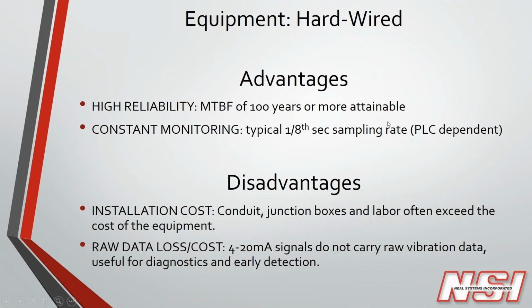So advantages of hardwired solutions, typically you're going to see an MTBF of 100 years or more can be attainable. What that means is you're not getting 100 years out of a sensor, but if you have 100 sensors in your facility and one failed per year, you'd be in line with a 100-year MTBF. And then for these hardwired solutions, you've got constant monitoring available. So your sample time depends on your PLC, but you have constant access to that data.